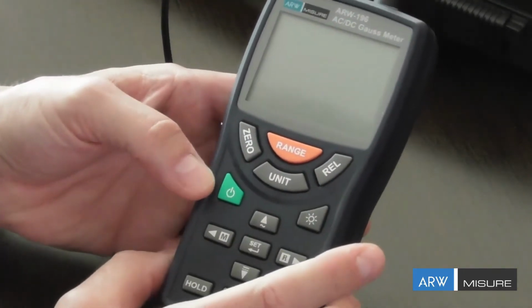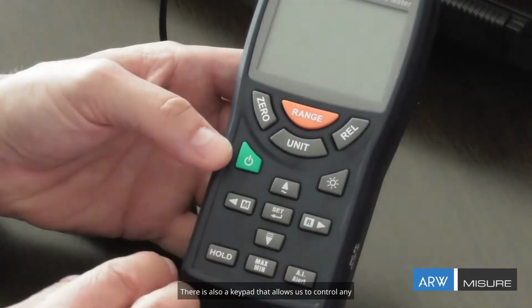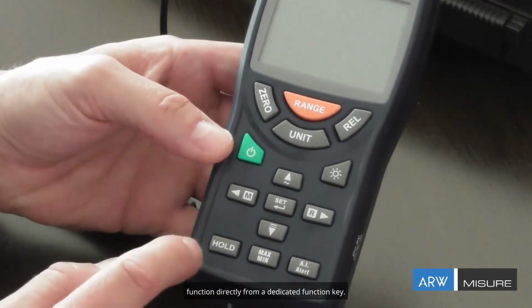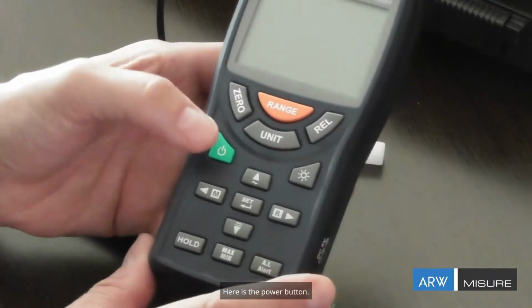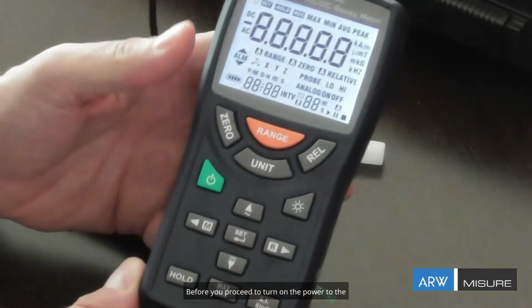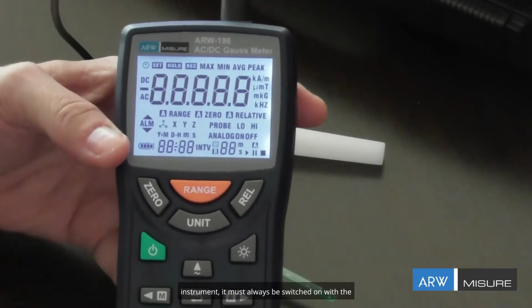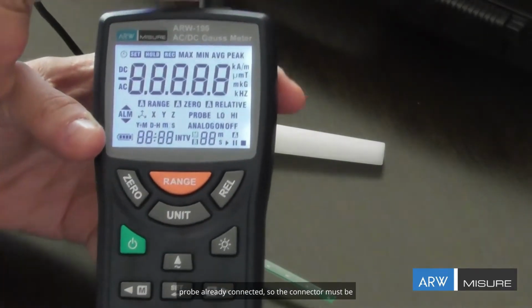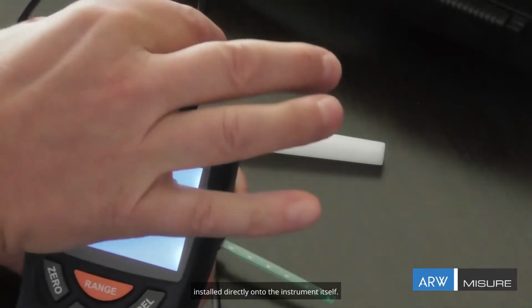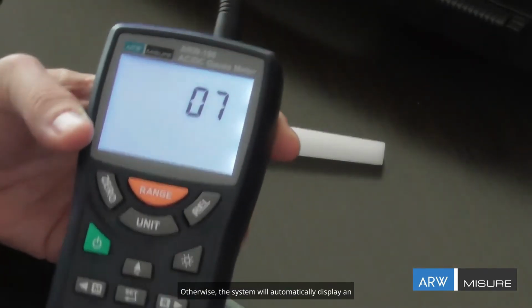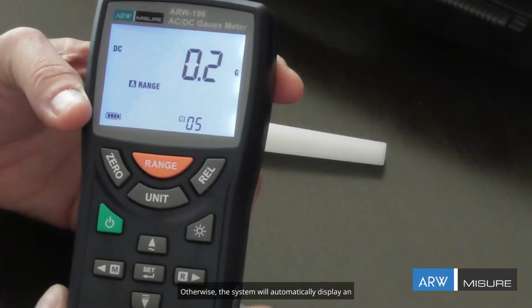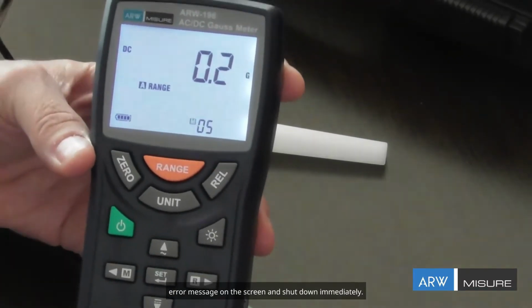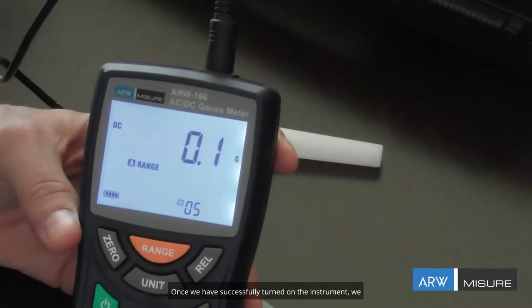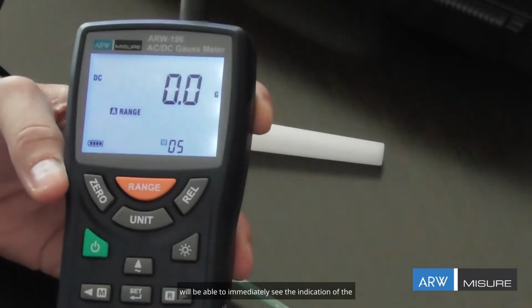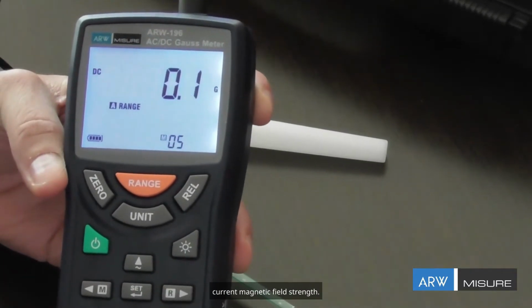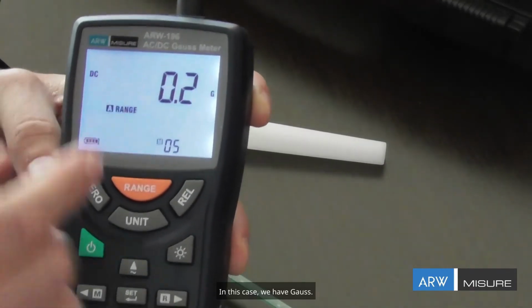There is also a keypad that allows us to control any function directly from a dedicated function key. Here is the power button. Before you proceed to turn on the power to the instrument, it must always be switched on with the probe already connected, so the connector must be installed directly onto the instrument itself. Otherwise, the system will automatically display an error message on the screen and shut down immediately. Once we have successfully turned on the instrument, we will be able to immediately see the indication of the current magnetic field strength. In this case, we have Gauss.